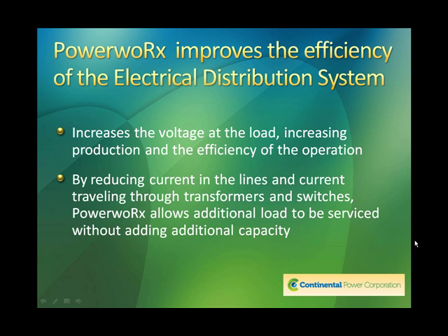But here's the key. By reducing current in the lines and current traveling through transformers and switches, PowerWorx allows additional load to be serviced without adding additional capacity. And this has been one of the reasons that PowerWorx has been sold over these 16 years many, many times. Maybe not the majority of the time, but certainly a very high percentage, because the facility is out of capacity. They have a 2,000 or a 5,000 amp service, and they're going to need to add more manufacturing equipment, and they have maxed out their service capacity. The transformer can only handle so much kVA, and they've exceeded that or are getting close to exceeding that, and they want to add more equipment.